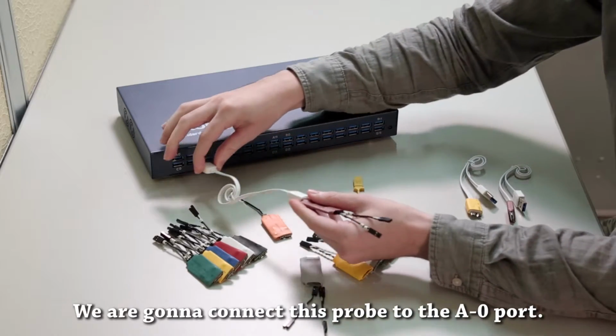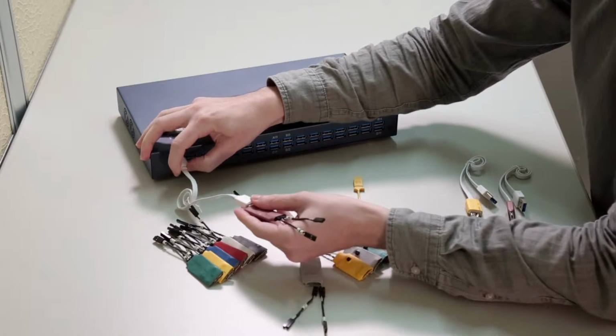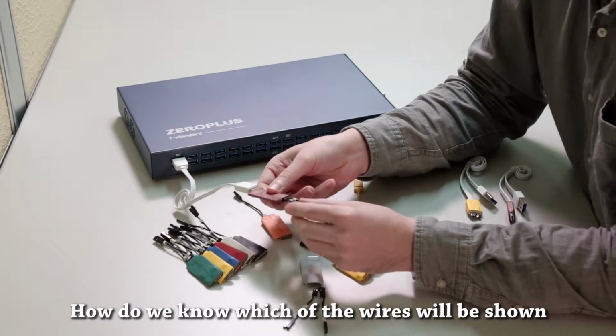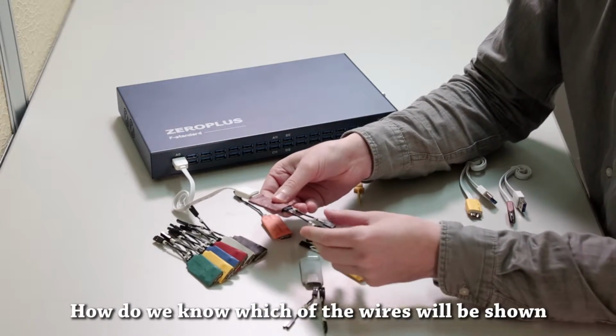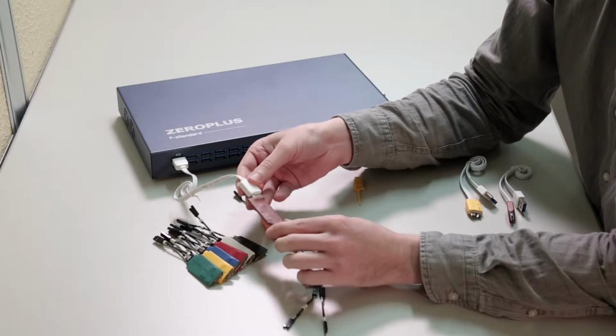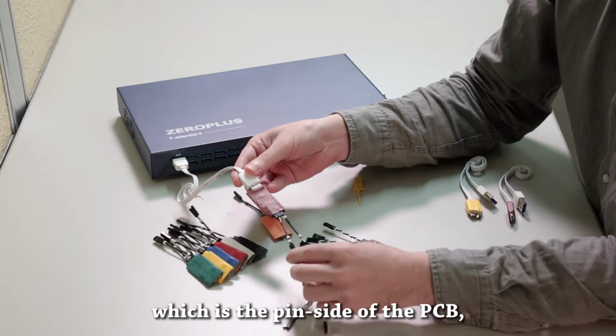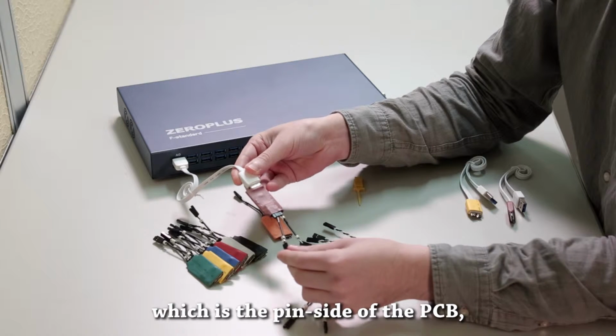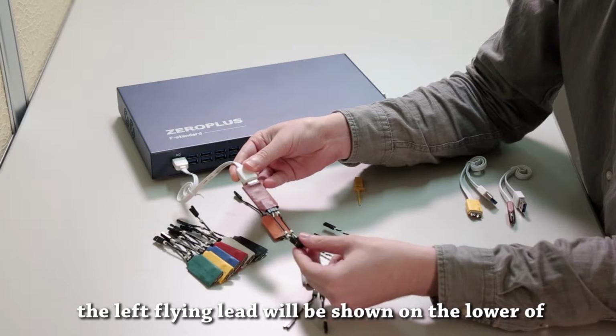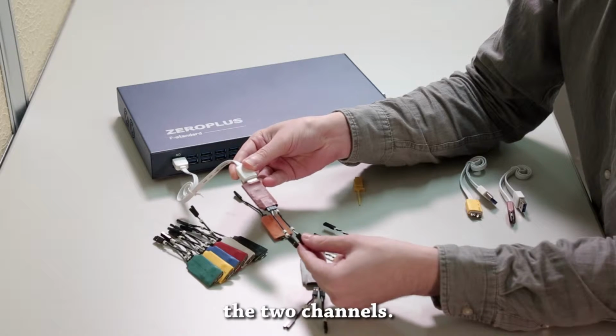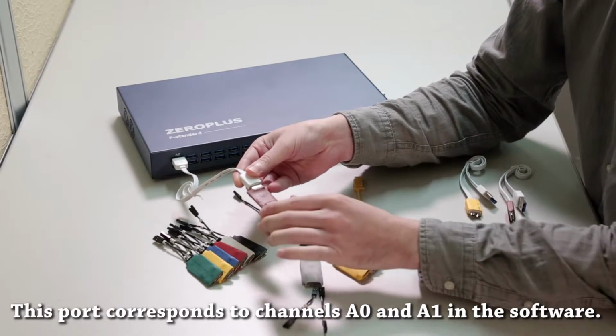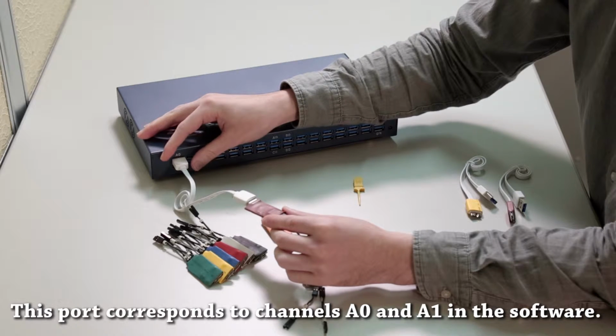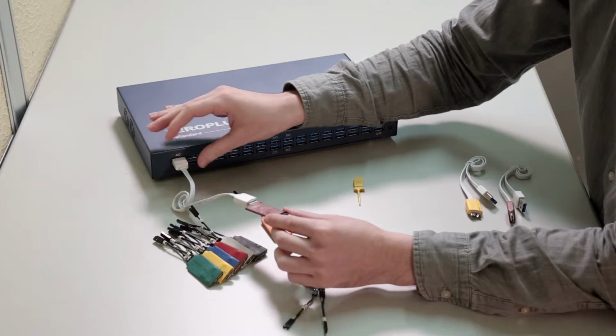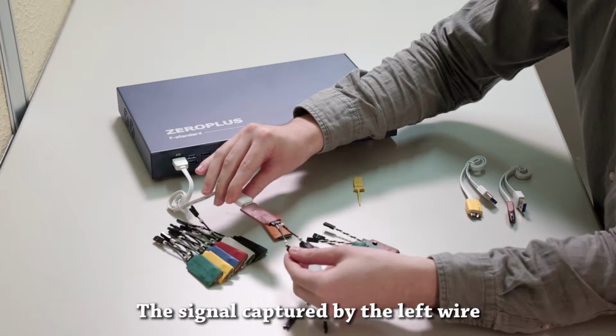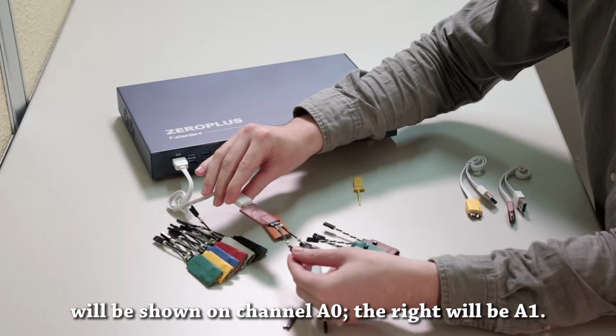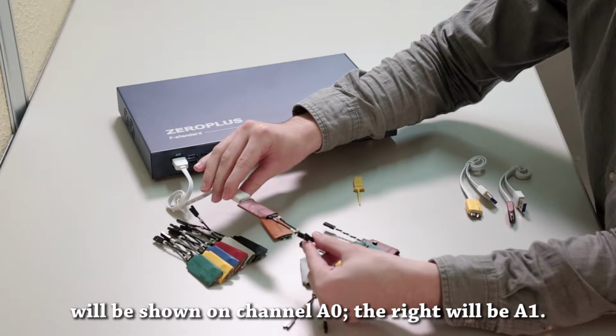We are going to connect this probe to the A0 port. Now, how do we know which of the wires will be shown as which channel in the software? When looking at the probe from the upside, the pin side of the PCB, the left flying lead will be shown on the lower of the 2 channels. This port corresponds to channels A0 and A1 in the software. The signal captured by the left wire will be shown on channel A0, and the right will be shown on channel A1.